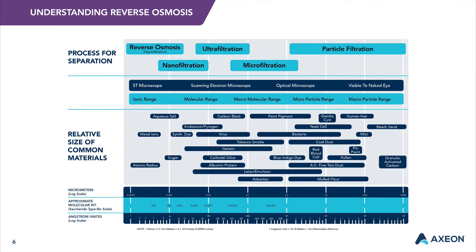The four categories are microfiltration, ultrafiltration, nanofiltration, and reverse osmosis. Reverse osmosis is among the finest levels of filtration available. The RO membrane generally acts as a barrier to all dissolved salts and inorganic molecules, as well as organic molecules with a molecular weight greater than approximately 100. Water molecules, on the other hand, pass freely through the membrane, creating a purified product stream. Rejection of dissolved salts is typically 95% to greater than 99%, depending on factors such as membrane type, feed composition, temperature, and system design.